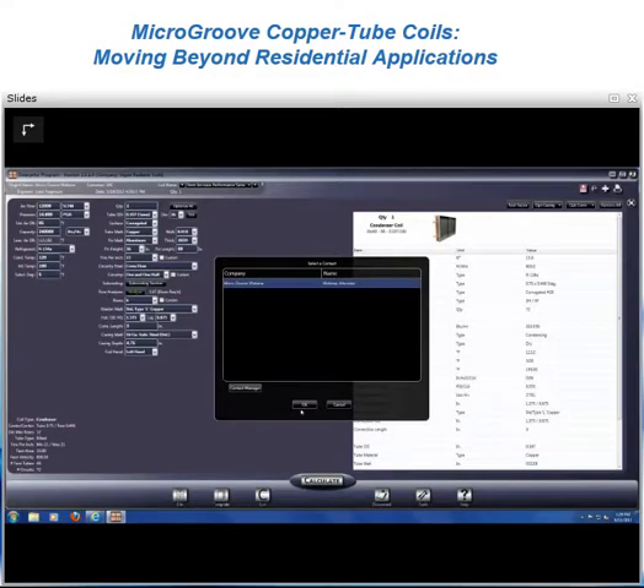So there's the 4 coils we've been looking at. And now here's our increased performance with the same face area coil at the bottom. Today's 5/8 or 3/8 coil at the top. We've increased our capacity by 20% while keeping the same fin side air friction. We do need to account for an increased refrigerant pressure drop in the system, but you're running a greater mass flow of refrigerant to the system. But we still have benefits in the coil weight. Coil is still 14% less than the original coil, 31% less refrigerant, and the copper weight is down by 29%. So you can see that there are significant benefits.